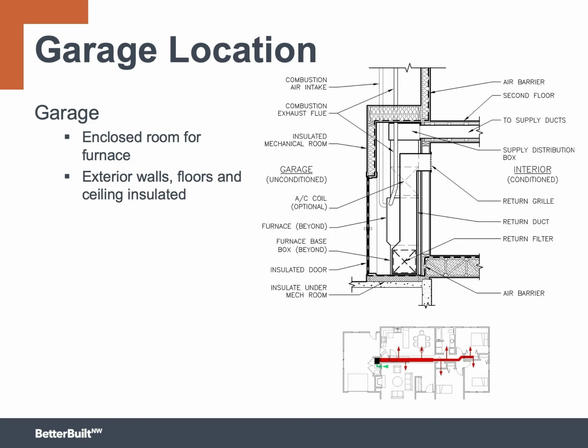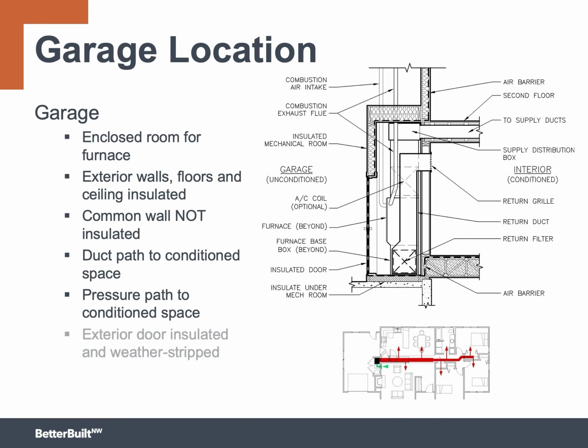Another way to accomplish this is to continue the floor framing from the house out over the slab so that you can fill that cavity with fiberglass or whatever insulation you're going to use, just as you would with the rest of the floor. Ceiling height may be an issue because you'll want to have enough space to get the supply ducts into the second-story floor. In this case, most of your ductwork is probably going to be in an open web floor truss between the stories of a two-story building. One of the things that you'll want to do is connect that furnace room thermally to the building itself. Leaving the wall between the furnace room and the house uninsulated is one way to accomplish this.